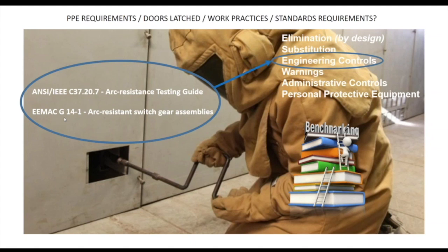One of the great engineering design things that could be put in place was in place in our power plants. All our 4160 13.8 kV switchgear was to a standard, EEMAC G14-1 arc resistant switchgear assemblies. That comes under the engineering controls, and they benchmark best practices. It was a great idea, and we did have an incident in the very early 90s where a 13.8 breaker did blow up, and no one got hurt because it was arc resistant switchgear. So there was less likelihood of a worker getting injured, and we didn't shut the whole plant down. It was just one breaker.